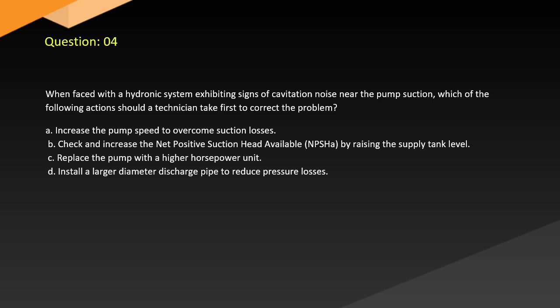A. Increase the pump speed to overcome suction losses. B. Check and increase the net positive suction head available, perhaps by raising the supply tank level. C. Replace the pump with a higher horsepower unit. D. Install a larger diameter discharge pipe to reduce pressure losses.